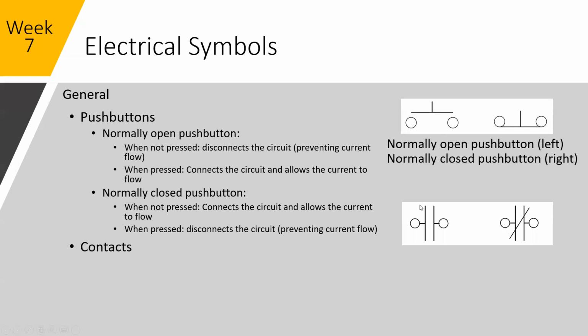Then contacts. You'll find contacts on almost all pieces of equipment when we're dealing with PLCs. These look like, if you remember from the ladder logic we were looking at and some of the other drawings, this would be a normally open contact, and this would be a normally closed contact. You're going to find these on relays, overload contactors, pump starters, any piece of equipment that might have a fault or a status that's going to be wired back to a PLC will have a contact of some sort.